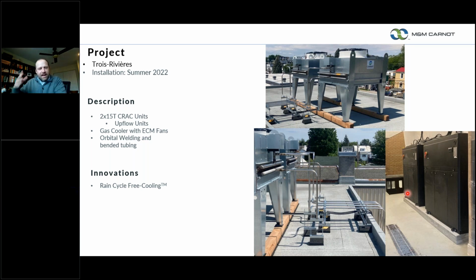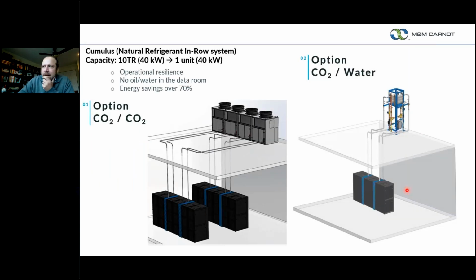Just wanted to show you a picture to kind of think about this. This isn't something that's extremely different than what you might be used to when you think about perimeter style cooling or air cooled technologies. One of the other applications that we have is row based cooling, and this is pretty unique because we have our gas cooler condensing unit, and then we have that hooked up to CO2 lines that go into your row based cooling unit. We were asked to design row-based cooling with CO2, and this was a design we came up with to basically allow for free cooling when we could, but also running CO2 lines directly out to the row-based cooling.